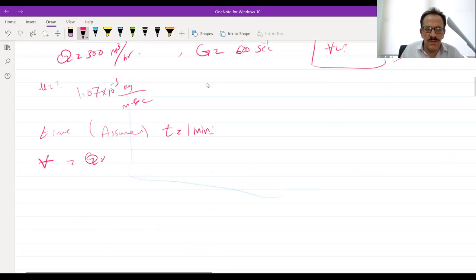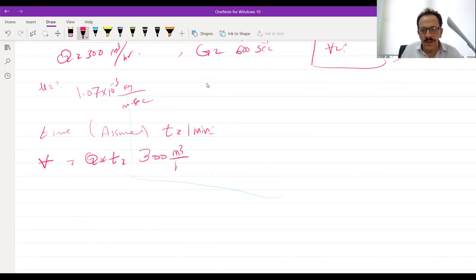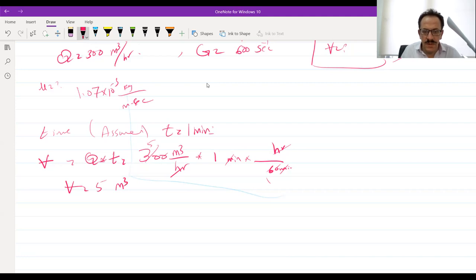For the tank, with one minute detention time, the volume equals Q times T. The Q is 300 m³/hour times one minute, converted by dividing by 60 minutes per hour. This gives a volume of 5 m³ for this tank.